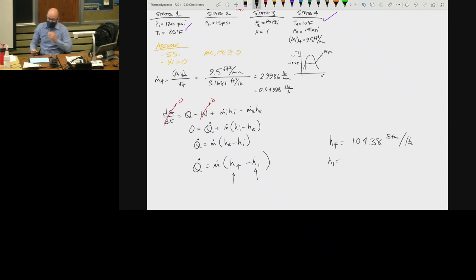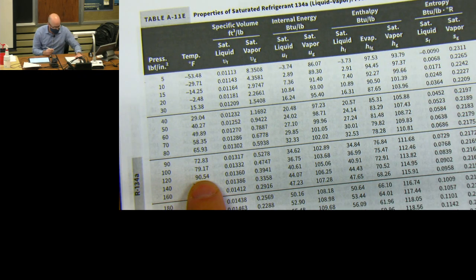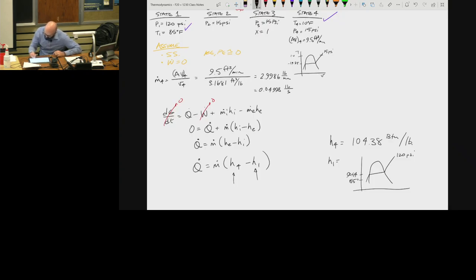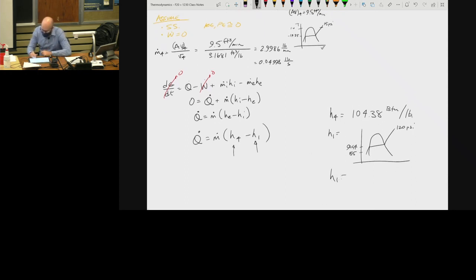H1, I'm going to have to figure out if it's a liquid, a vapor, or a liquid-vapor mixture. So I'm going to draw my vapor dome, and say it's 120 psi. At 120 psi, I know we saturate at 90.54. I know my temperature's at 85, so I'm a liquid. There are no liquid tables for R134A, so I have to say that H1 is approximately equal to the saturated liquid enthalpy at the temperature of 85 degrees Fahrenheit.